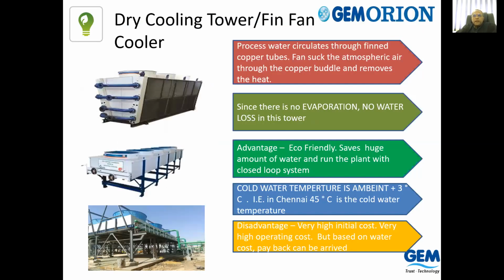Now coming to the dry coolers. See, dry coolers are used where the ambient temperatures are high. So when the required temperature is above the ambient, then we can adopt this. Here the water will be circulating in a closed loop, so zero evaporation, and you can get as low as ambient plus 3, and with extended operation we can get up to ambient plus 1 or 2 degrees, but it becomes unwieldy in size and technically, and the air fan power also becomes very high. But here the advantage is if there is no water at all, then we can use this system.